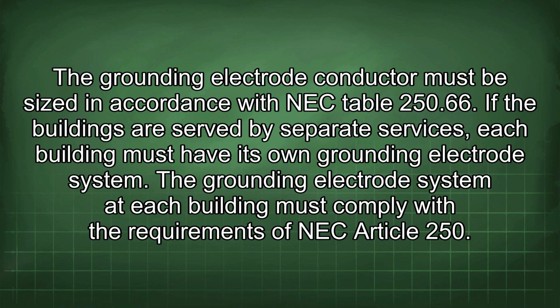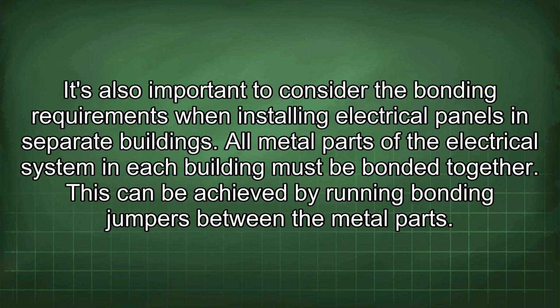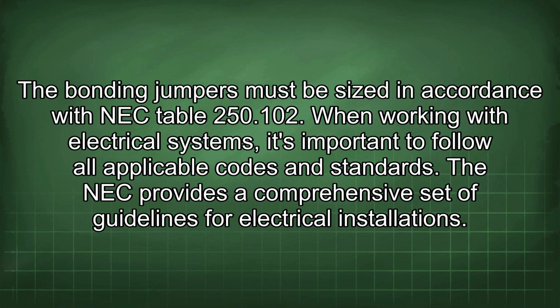The grounding electrode system at each building must comply with the requirements of NEC Article 250. It's also important to consider the bonding requirements when installing electrical panels in separate buildings. All metal parts of the electrical system in each building must be bonded together. This can be achieved by running bonding jumpers between the metal parts. The bonding jumpers must be sized in accordance with NEC Table 250.102.